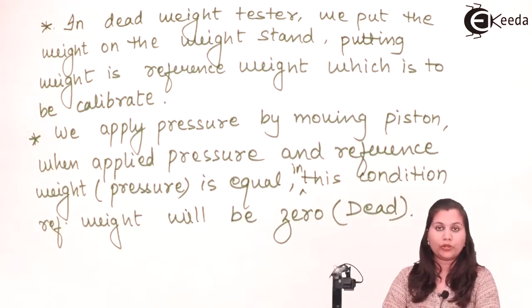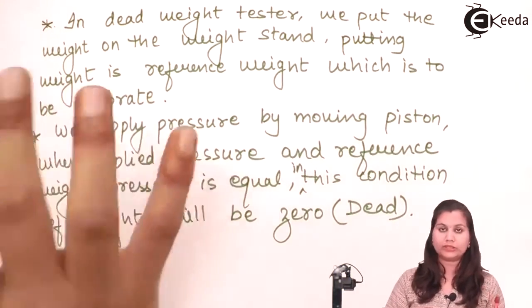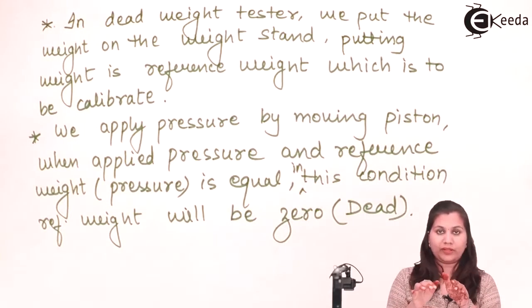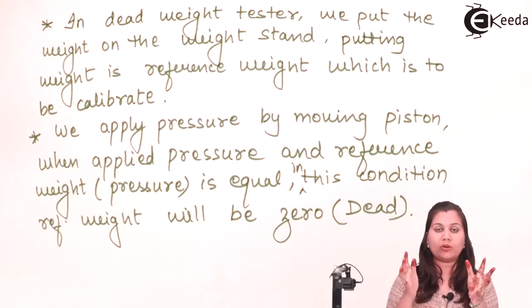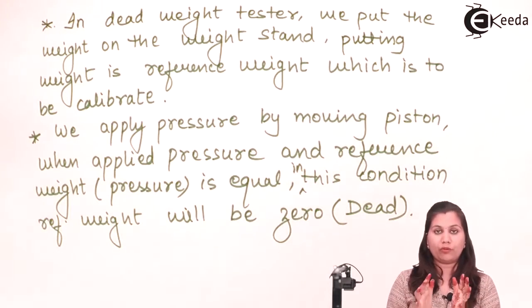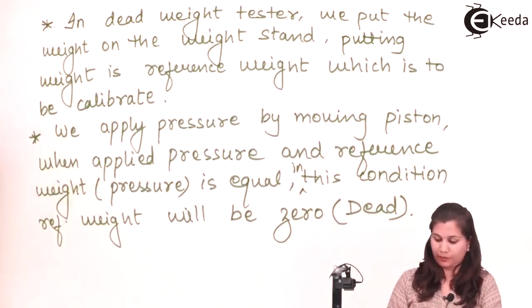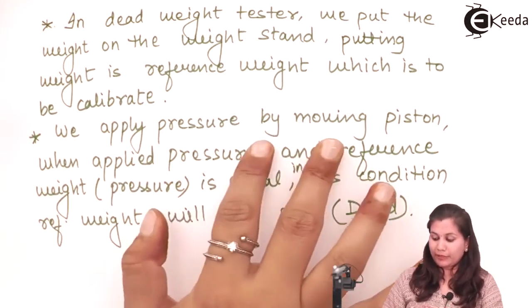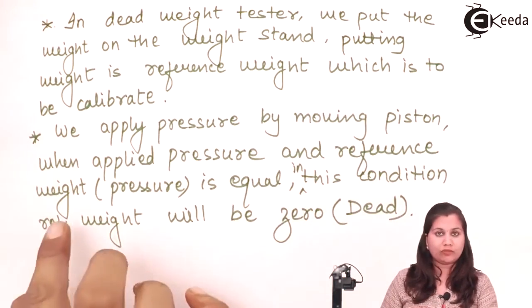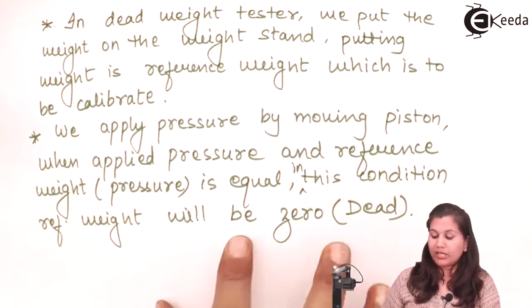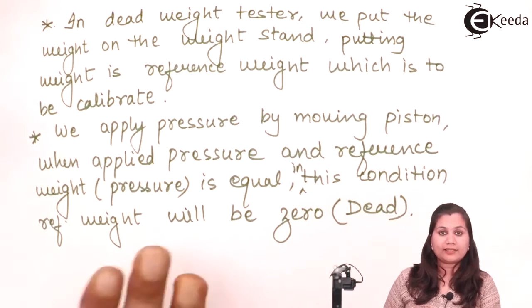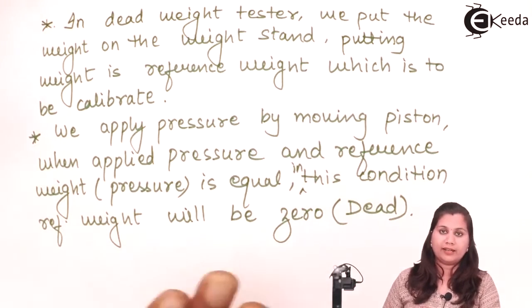So in a dead weight tester, we put the weights on the weight stand. The weight which is put on the weight stand is the reference weight, or we can also say it is the pressure which we want to calibrate, or the pressure measuring device which we want to calibrate. So this is the reference weight or the reference pressure. Now after that, we apply the pressure by moving the piston. When the applied pressure and the reference weight or pressure are equal, in that condition the reference weight will become zero, or we can say dead, and that is why it is called a dead weight tester.